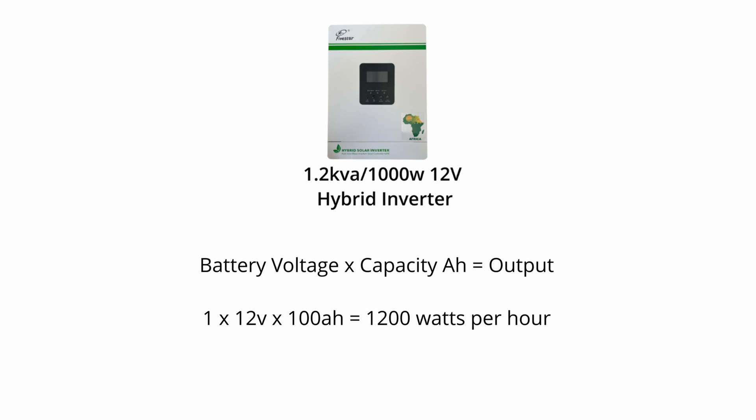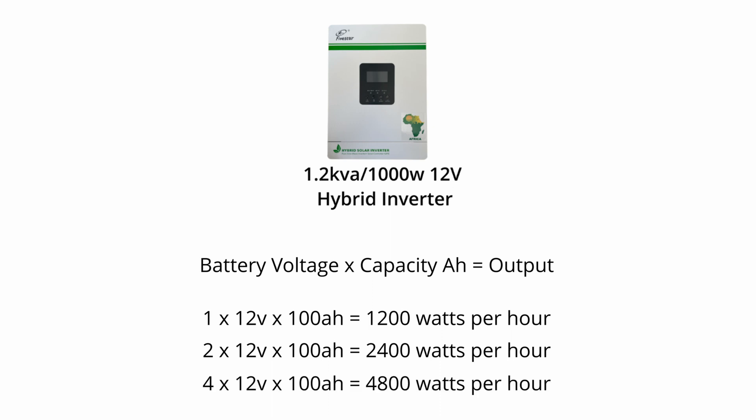The next question is: how do we calculate what the battery system is capable of doing? To calculate the output of the batteries, you take the battery voltage of the system and multiply it by the capacity in amp hours. So for example, if you have one 12 volt battery at 100 amp hours, the system would be capable of doing 1200 watt hours. Two batteries: 2400 watts. Four batteries: 4800 watt hours.